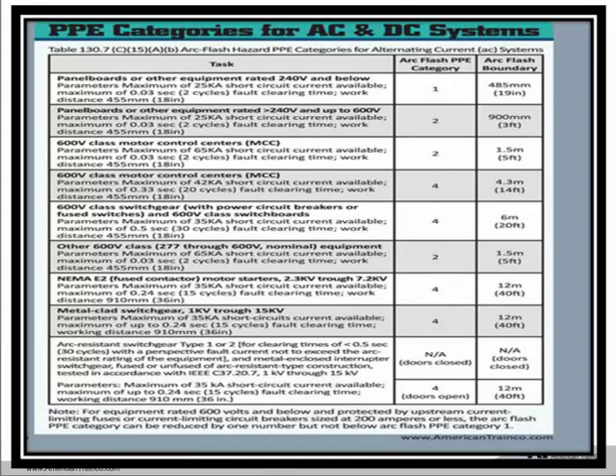So these are the PPE categories. We understand that they did delete arc flash PPE category 0. It's no longer there. This table becomes very important when we approach a piece of equipment and there is no label on that equipment. We are going to have to make sure that first we answer those questions. Do we need arc flash PPE? If the answer was yes to any type of particular equipment I walk up to, the next table we would go to is this table.